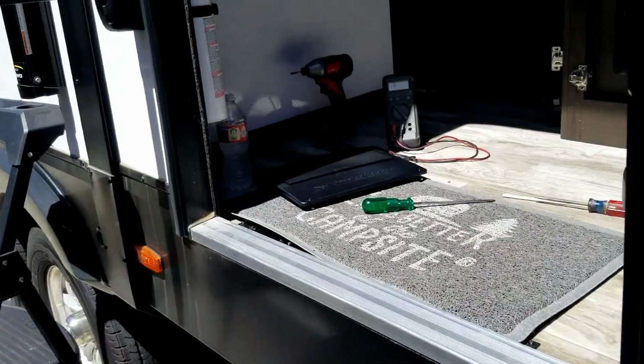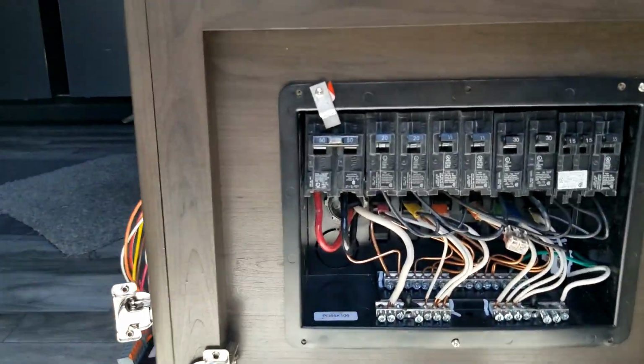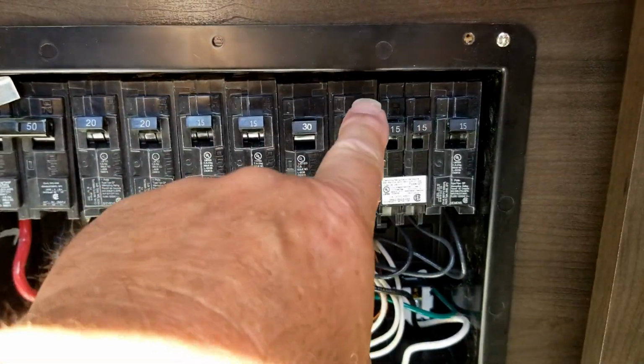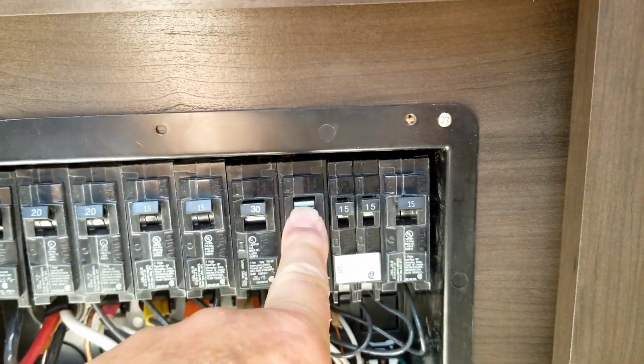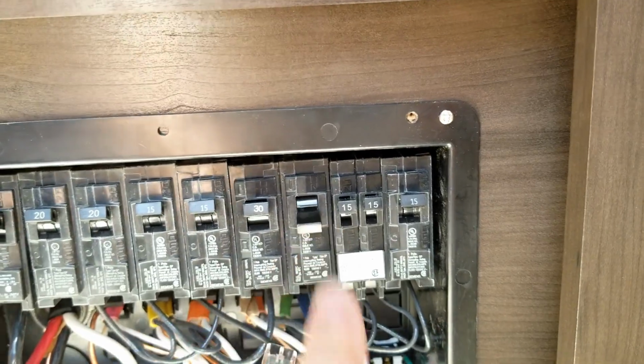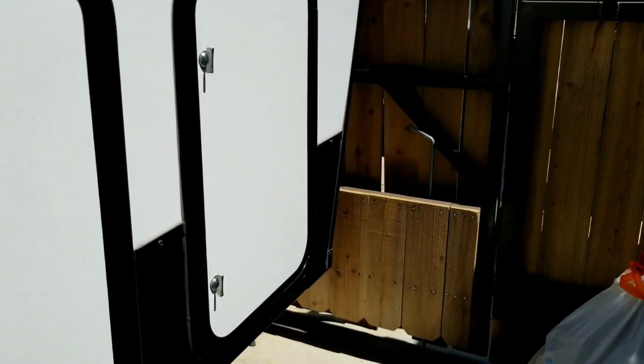So if I take my tester, this wire is currently live. So what I'm going to do, I'm going to walk around and I'm going to turn off the 30 amp breaker that's coming back from that loop in the front. And I want you to notice what happens. So now when I take my tester, this wire is still live.